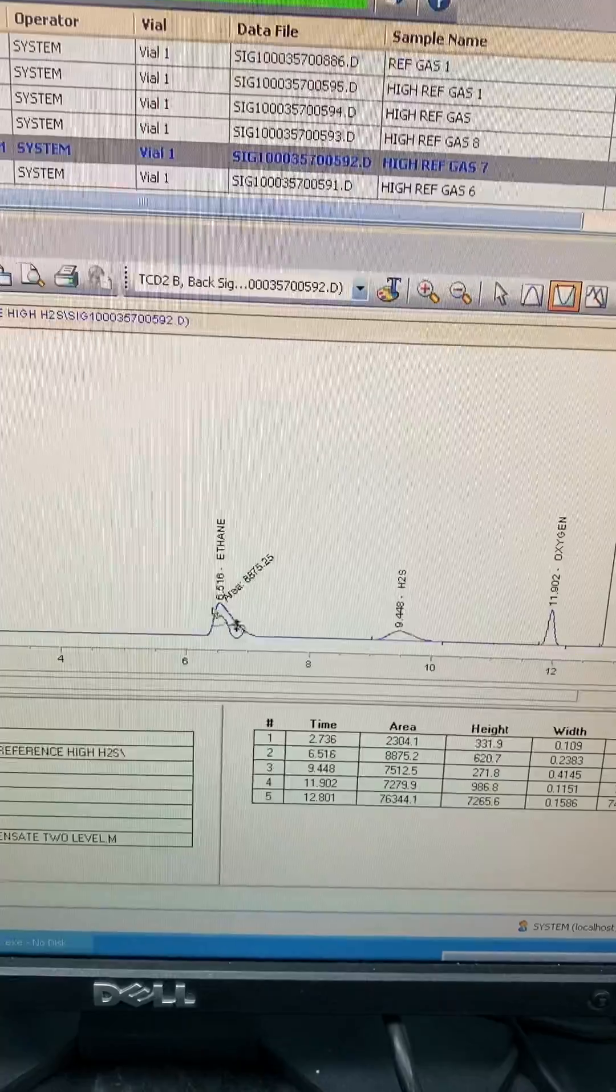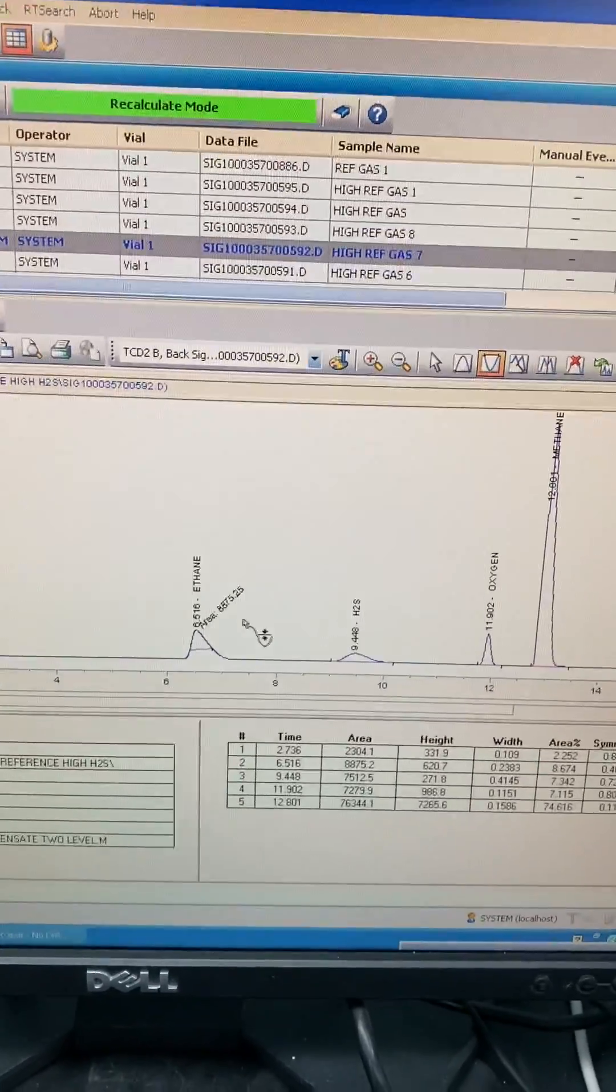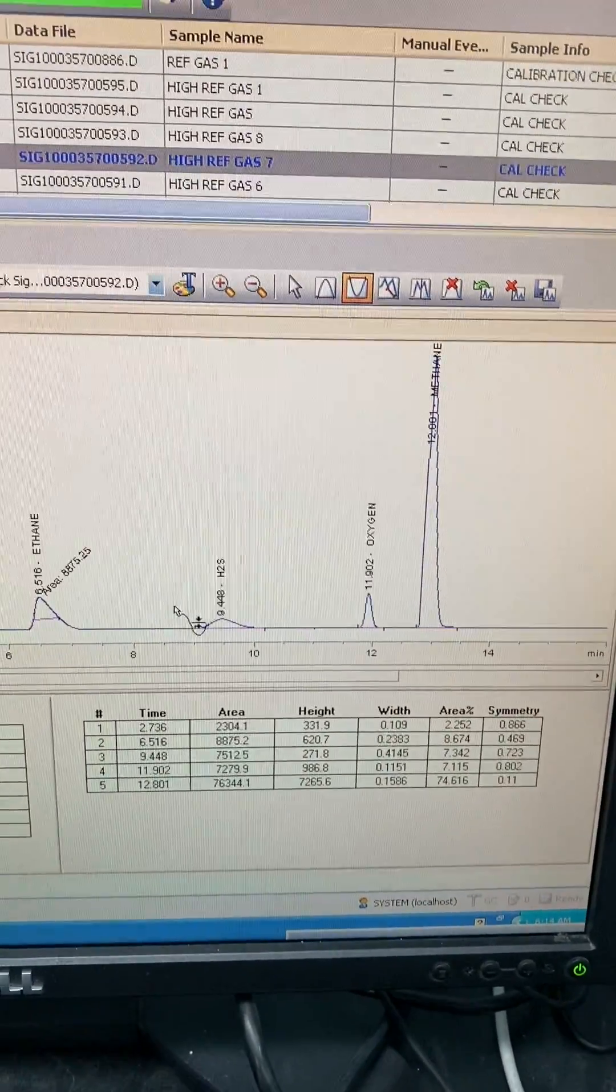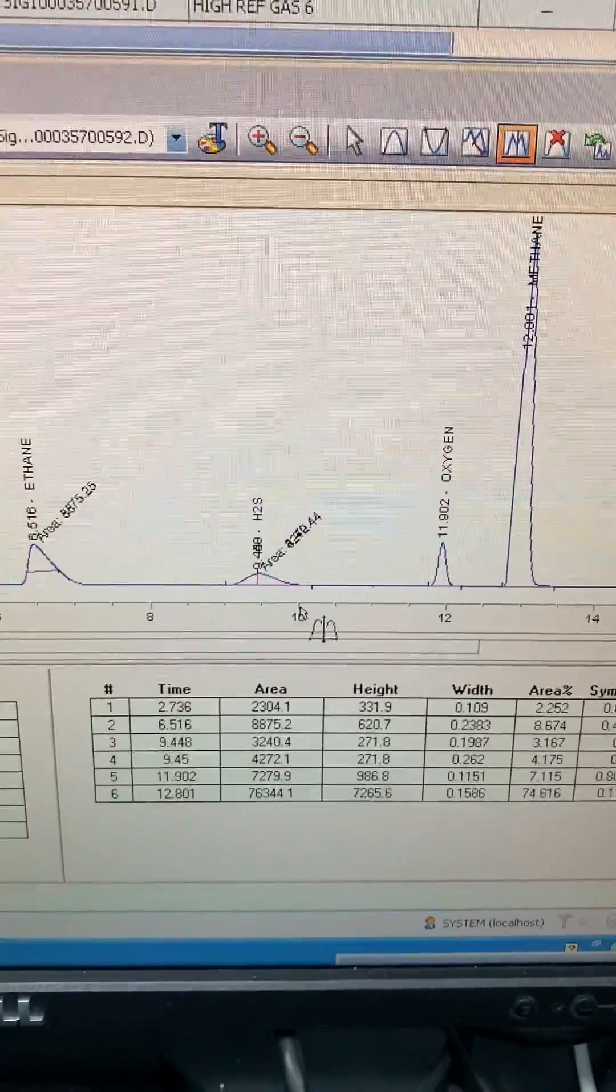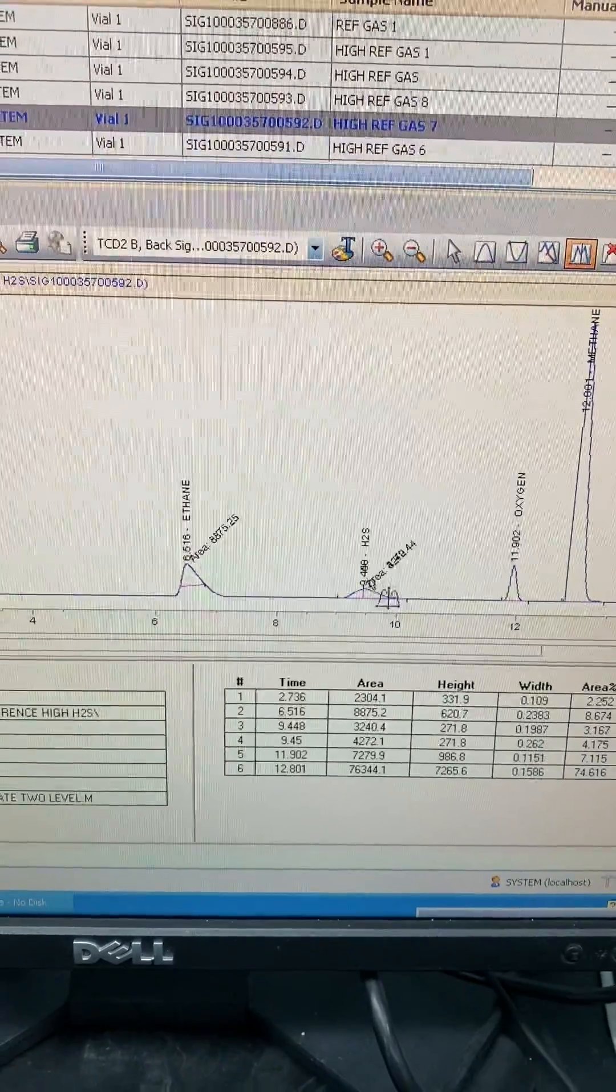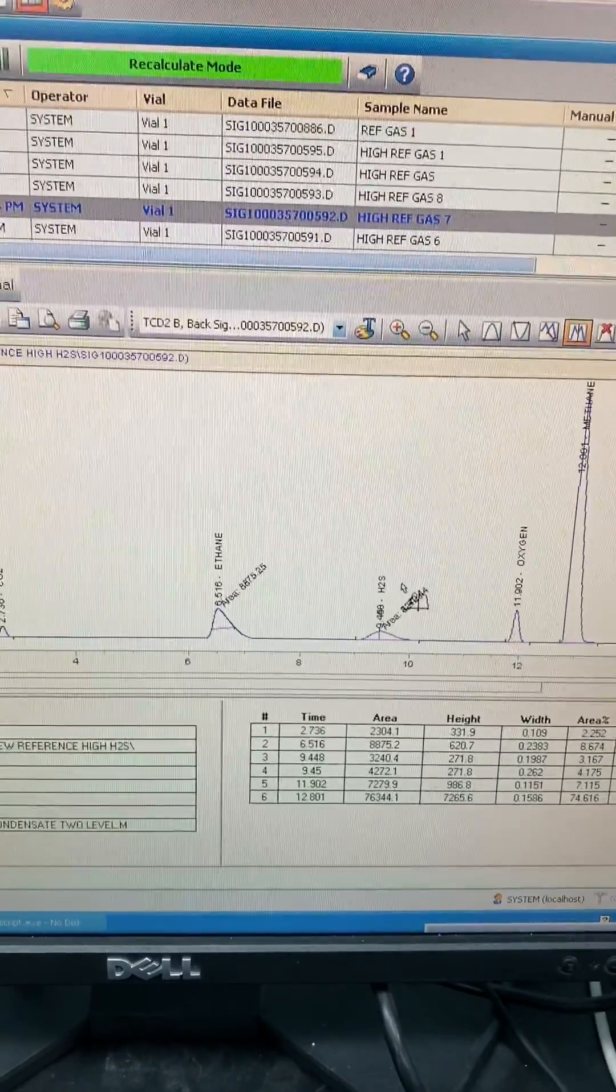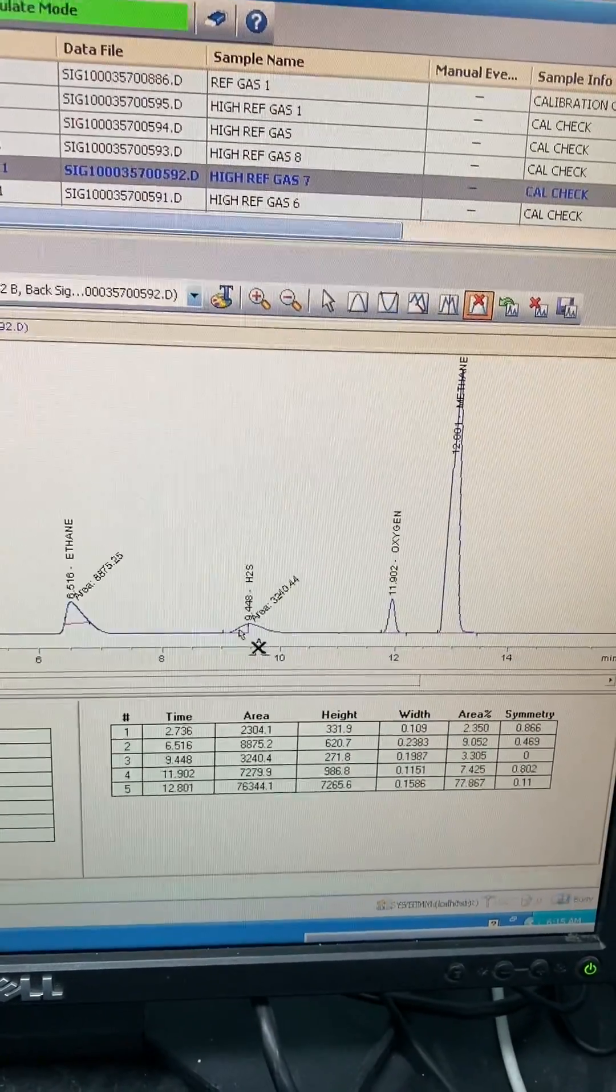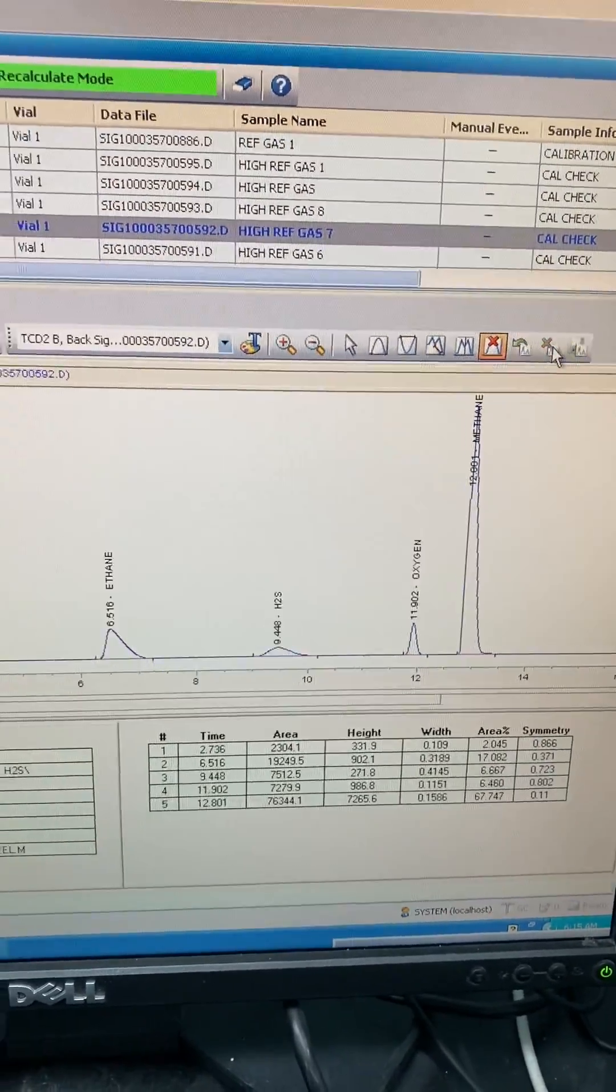For here, you will make like baseline. So I wanted the baseline for this peak to become this one. So it's like manual integration for the peak. Sometimes you use these features. If you have a noisy baseline, you can do it and make your own peak area. Imagine that I have one broad peak like H2S and water sometimes overlap to each other. So you can split the peak. I want this to be two peaks. In this case, you will have two peak area with two retention time. And then in your calibration table, you will put for this peak like H2S and this one water or vice versa or whatever you want. This action, you can delete the peak at all. So it will not be integrated. It will not be identified.